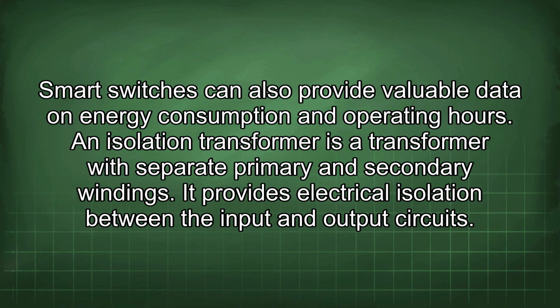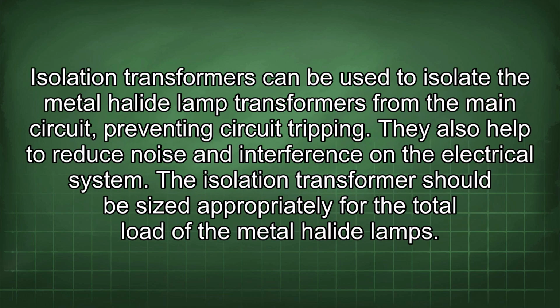An isolation transformer is a transformer with separate primary and secondary windings. It provides electrical isolation between the input and output circuits. Isolation transformers can be used to isolate the metal halide lamp transformers from the main circuit, preventing circuit tripping. They also help to reduce noise and interference on the electrical system. The isolation transformer should be sized appropriately for the total load of the metal halide lamps.